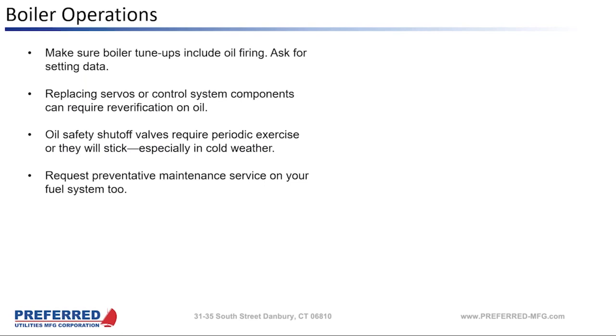And then our technicians do a lot of preventive maintenance on fuel systems. Here in the Southeast, where we're concerned about hurricanes, we do most of our fuel system PMs in May and June, right before hurricane season. Alex, where you're at, it's more in the fall, correct? Yeah, it depends. If it's more of a boiler plant or a generator application, definitely recommend PM service though, even if it's a generator application. I think a lot of people assume the generator rep is looking at the fuel system, and that's just not the case. You're going to want to have a dedicated PM set up for that, and we can help put together a PM checklist or whatever it is you need for documentation, but it's really important.